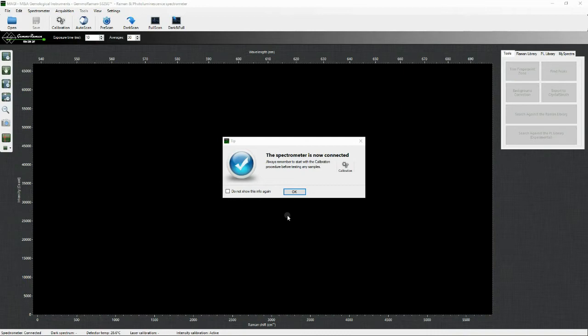A pop-up window will appear on the computer screen. The unit is ready for the initial calibration. This procedure is required before starting to collect spectra, because the laser needs a bit of time to warm up, and hence to provide the correct wavelength beam. The calibration procedure should be repeated 30 minutes after the unit has been turned on. By that time, the laser should have reached the correct working temperature, and there will be no need for more calibration afterward. The software is provided with an automatic countdown that warns the operator every 30 minutes to perform a new calibration procedure if needed.